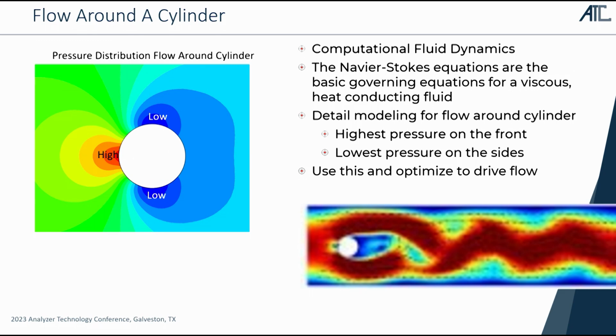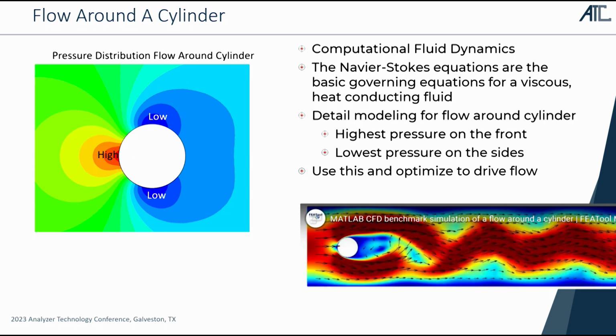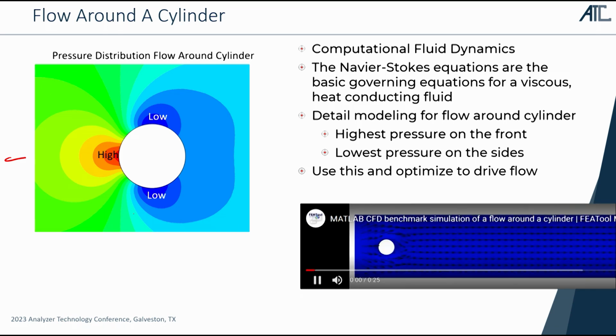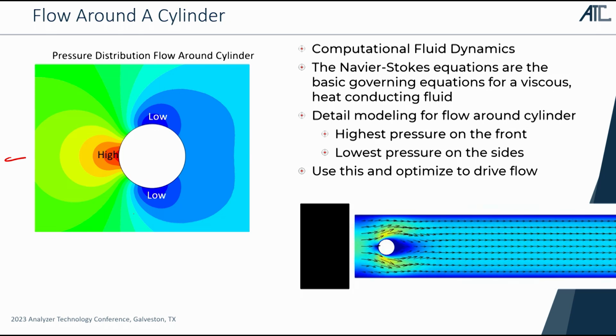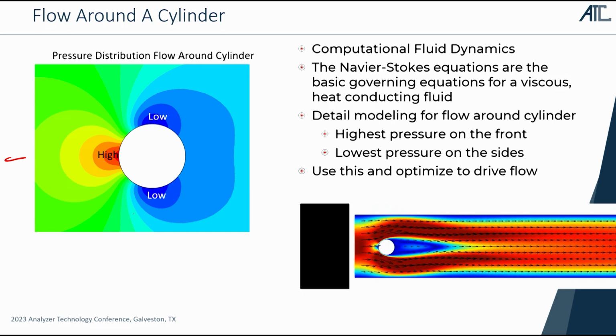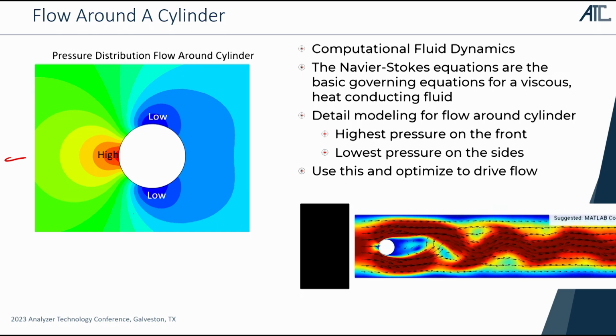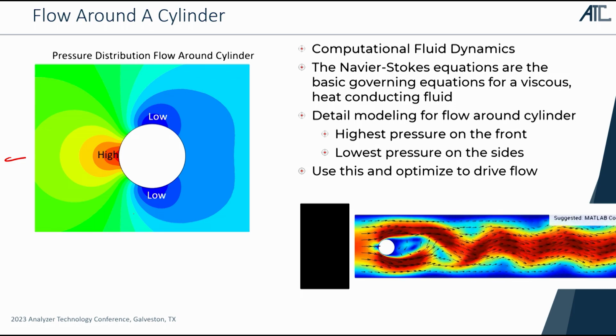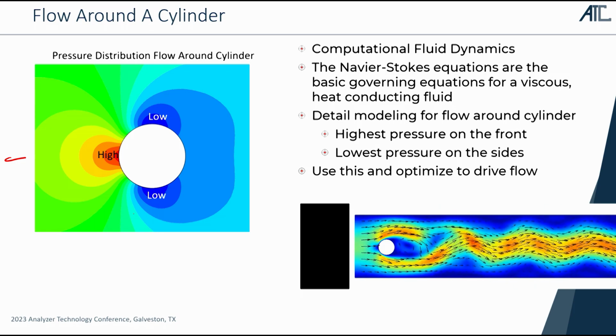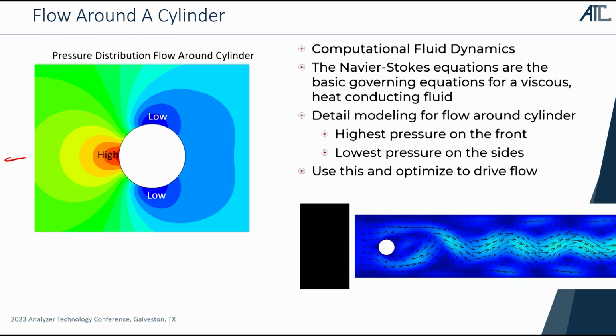So again, if I am flowing around a cylinder, if my direction of flow is going this way, oops, I just triggered my video before I wanted to. Oh well, we'll watch the video then. The bottom video is a mathematical simulation of flow in a pipe. You can see what happens as the flow increases: the red zones are where low pressures are building up on the sides. There's a little blue spot right at the front, in front of that probe, which is actually a low pressure zone. And then you see the Karman vortices forming. These are the things that cause flow probe resonance, and then they slow the flow back down again. It's a cool little video. YouTube has all sorts of great ones for flow around cylinders.